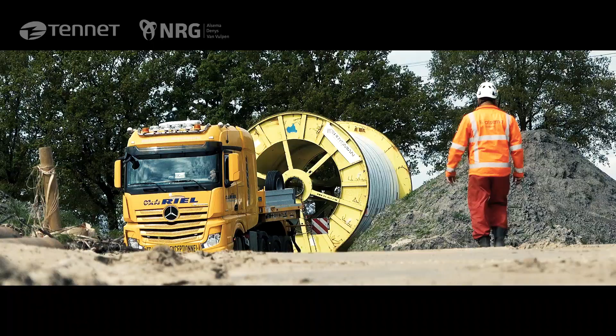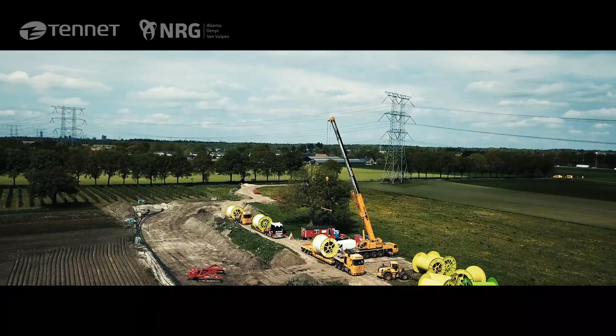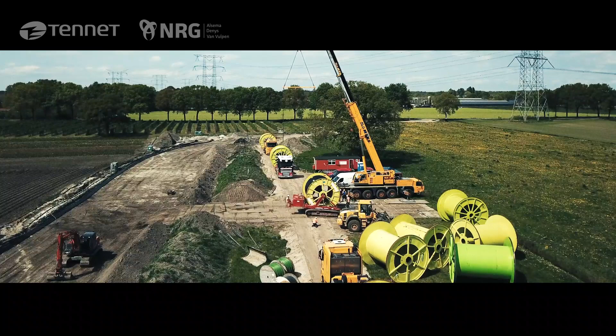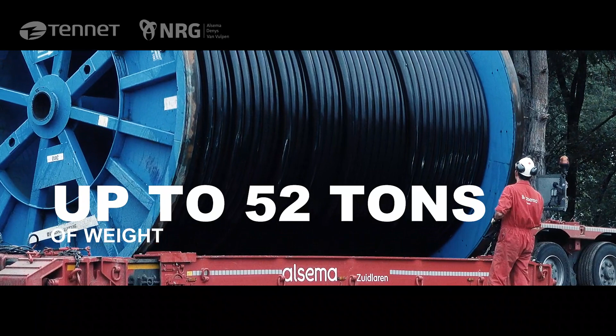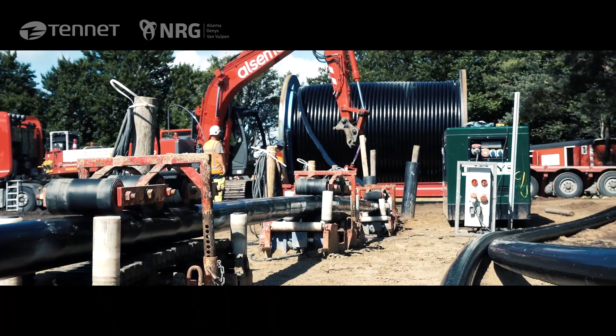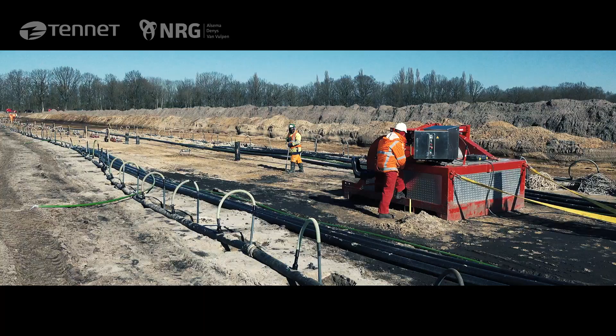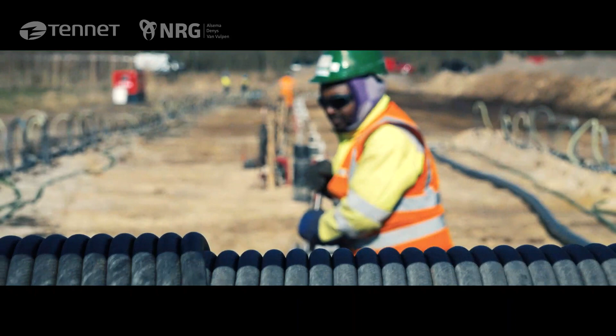The longest ever land cable was laid as part of this project. A 2,500 meter long, 150 kilovolt, 2,500 square millimeter cable. NRG transported and laid this cable using a special reel trailer. At weights of as much as 52 tons, it takes strength and discipline to pull cables through the protective pipes. During this process, all the details, such as speed and power, were carefully monitored and recorded.